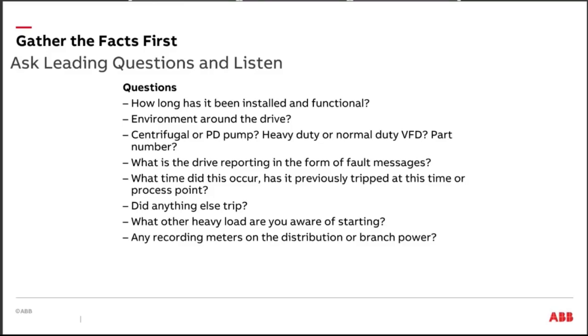Or I like to know, am I on a conveyor? Am I on a screw? What's the actual application? What are we doing with this thing? If the drive is tripping, give me the fault message, common sense. What does the drive think's going on? Okay. And then you have to think about it yourself. Well, does that make sense? Is the drive trying to tell me one thing and maybe I know this is going on?